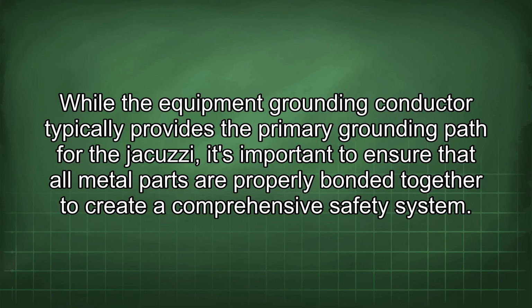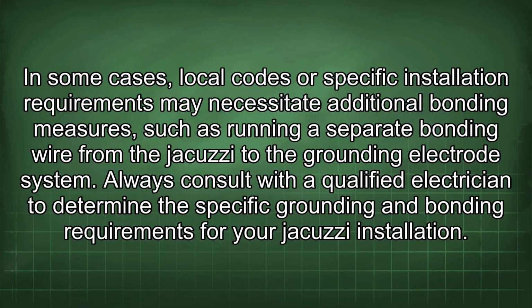While the equipment grounding conductor typically provides a primary grounding path for the jacuzzi, it's important to ensure that all metal parts are properly bonded together to create a comprehensive safety system. In some cases, local codes or specific installation requirements may necessitate additional bonding measures, such as running a separate bonding wire from the jacuzzi to the grounding electrode system. Always consult with a qualified electrician to determine the specific grounding and bonding requirements for your jacuzzi installation.